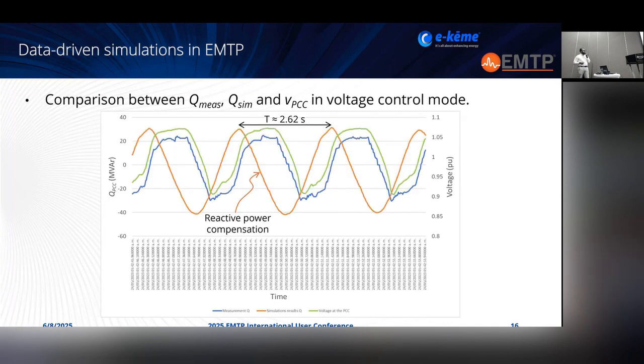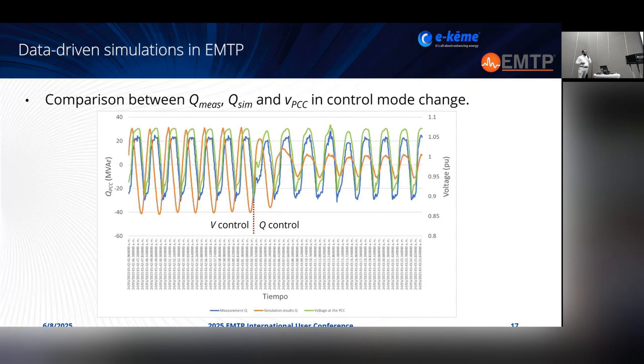On the last slide, this was the part on the voltage control mode. As I said, the power plant was compensating the reactive power oscillations in this control mode. On the other hand, once the control mode was changed, the oscillations were dampened, and we can see the reactive power entering in phase with the voltage, but these oscillations are not fully dampened, so other actions must be taken to compensate this voltage oscillation.